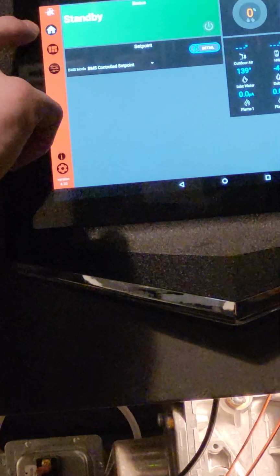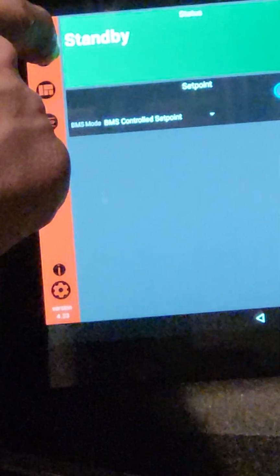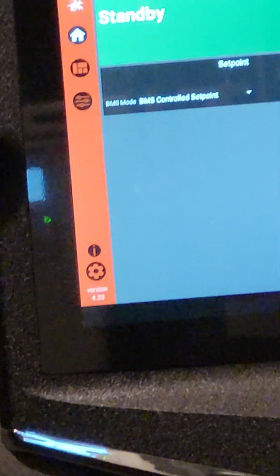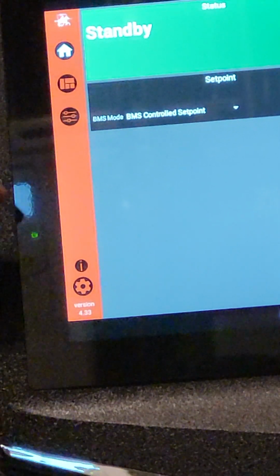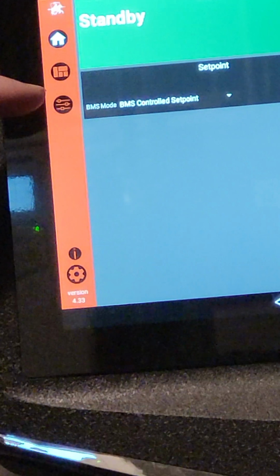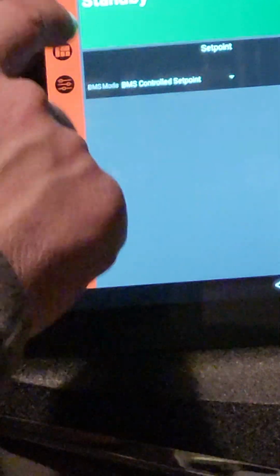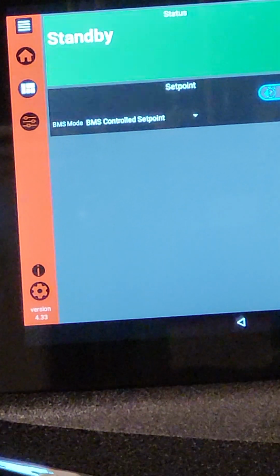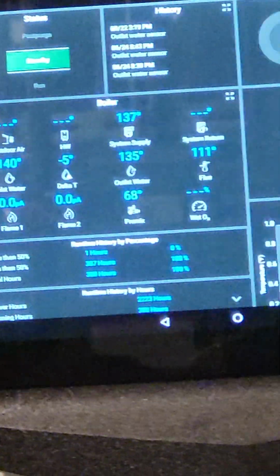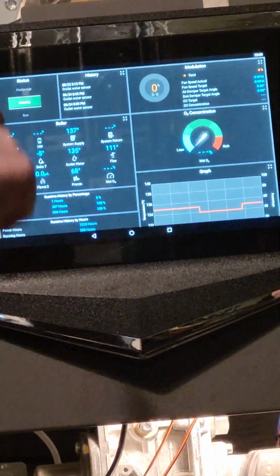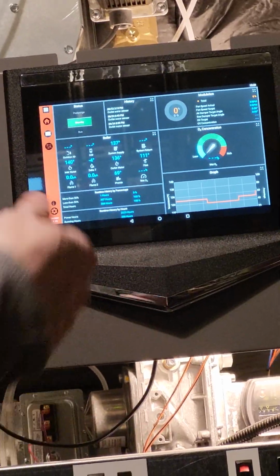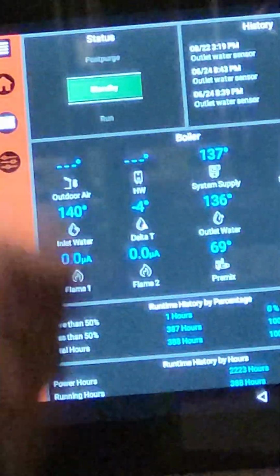So in the top left corner here, you've got a home button. That's our home screen. That's the top circle. That's what we're at right now. There are 3 circles: home, view, and then installer. So if we press the view button, it opens up a different menu. Now this is a touch screen with a slider. Nice. So status shows us where we're at. Standby, if it was running, it would say run. If it was in pre-purge, it would say pre-purge. So it tells you what it's doing right now.